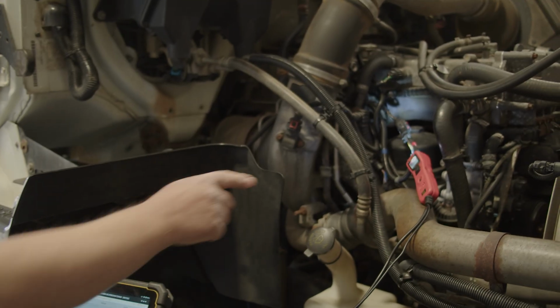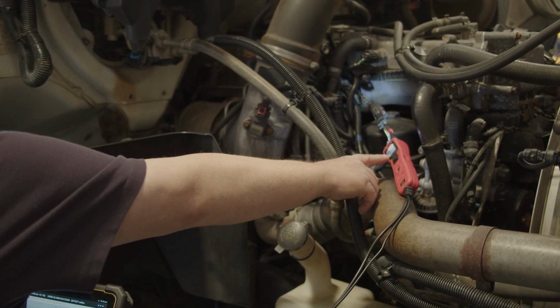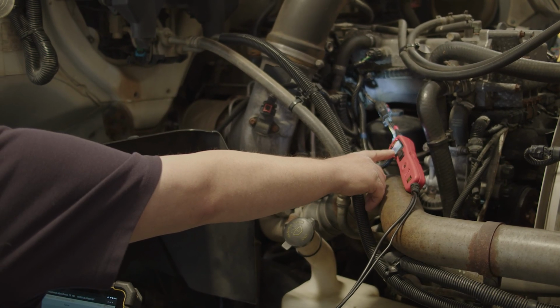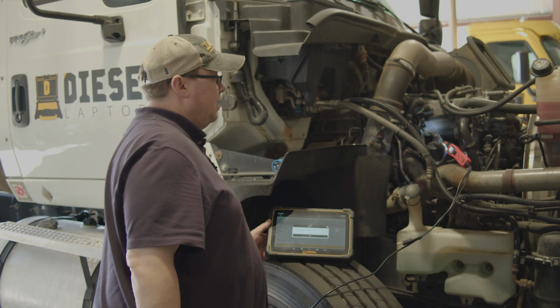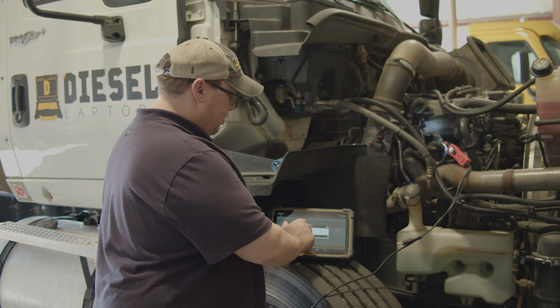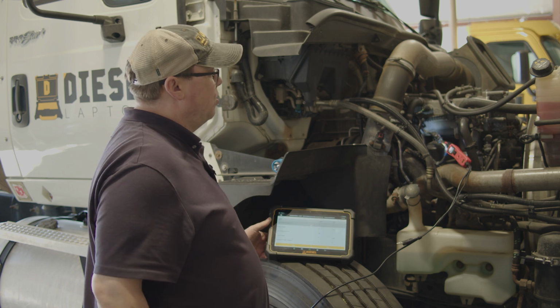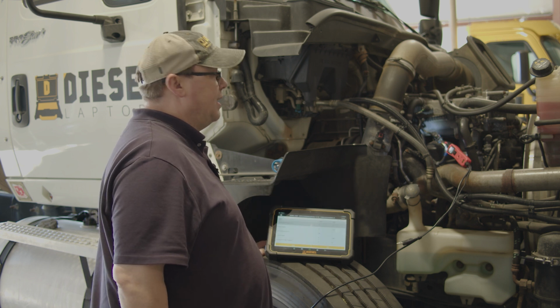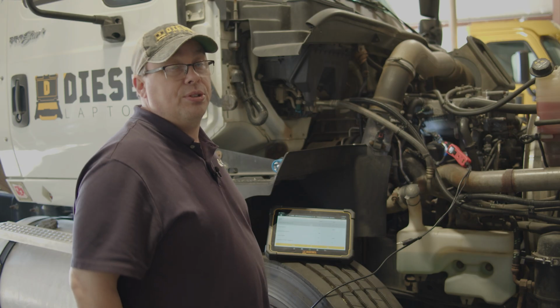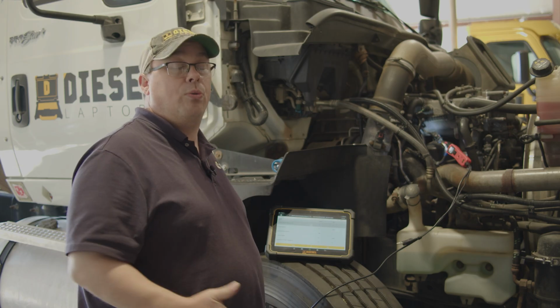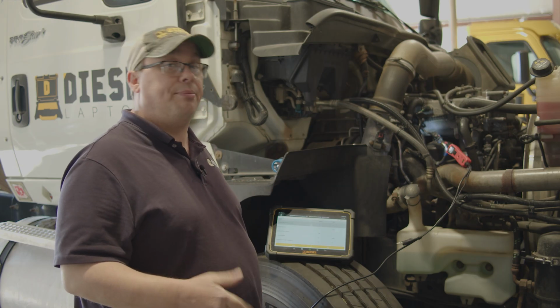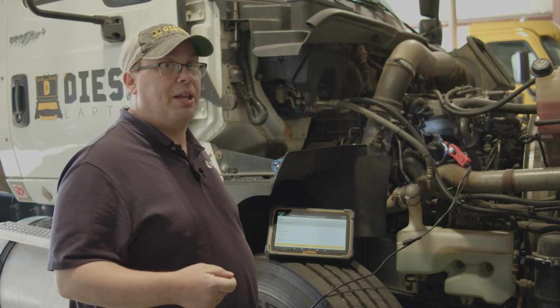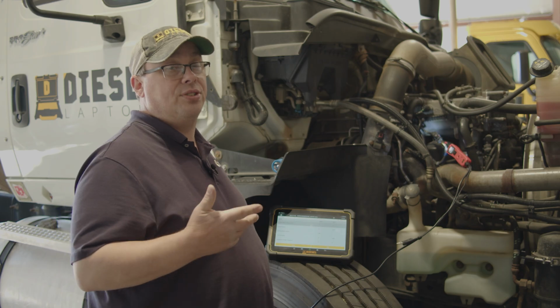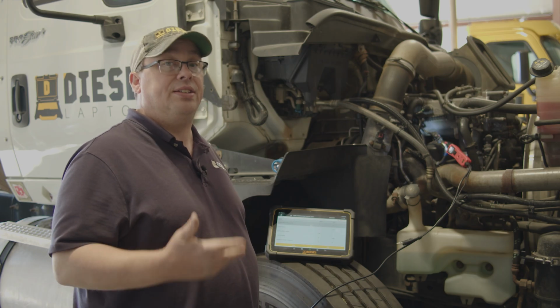And as we can see, it looks like I have an issue with that ground circuit. If you notice, when I did the test, my voltage didn't go all the way down to 0 volts. It was floating above at about 1.1, 1.2 volts, and my green light was flickering a little bit. So what that is telling me, ladies and gents, is that I have some resistance in this ground circuit.